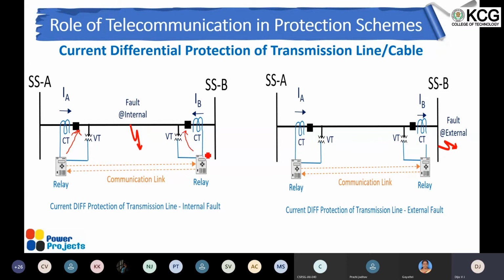And if the fault is external, we have already seen that the resultant current will not be there, because both CTs will be seeing the same current. So no need to worry about that resultant current. Yeah, so that's the scheme.